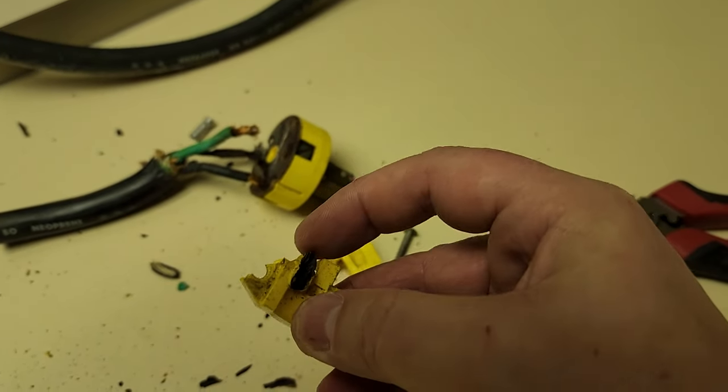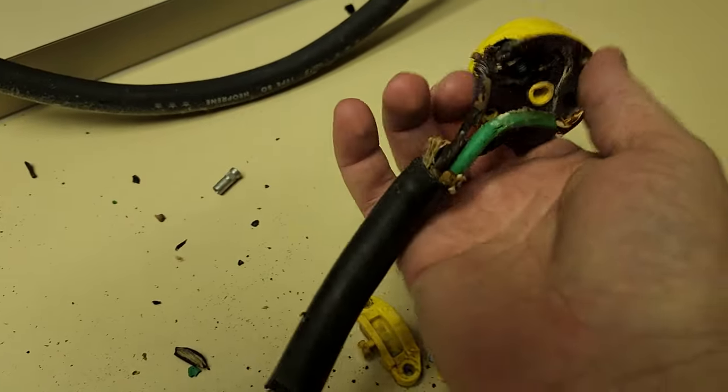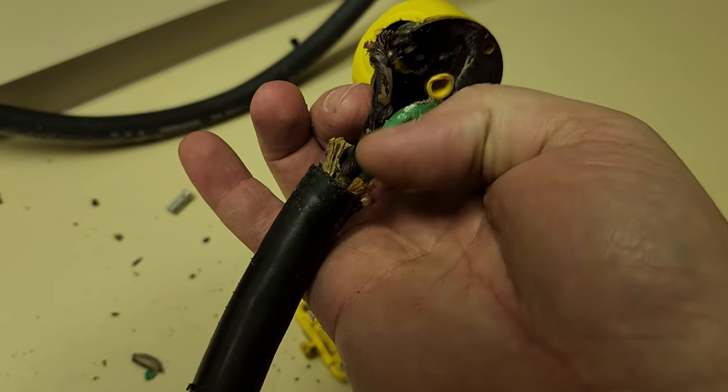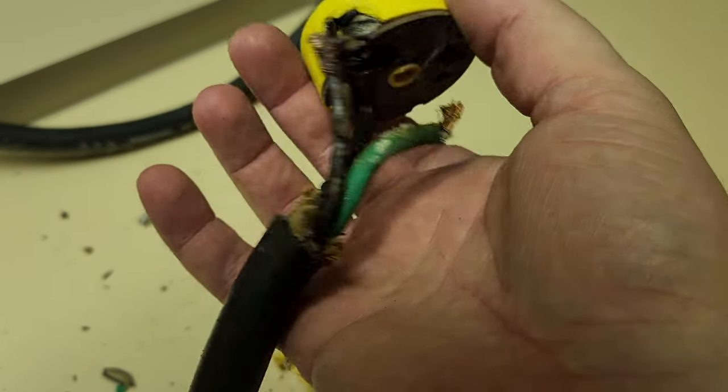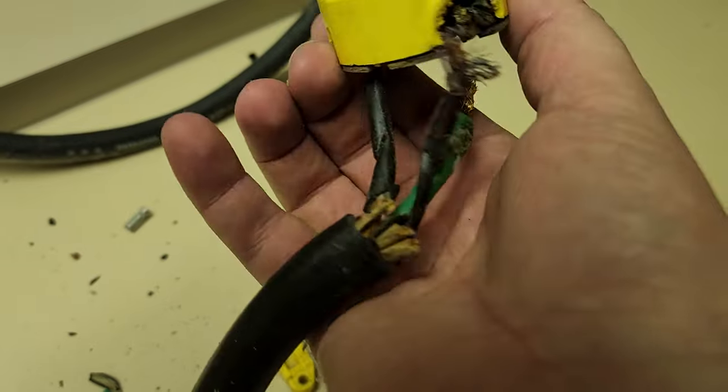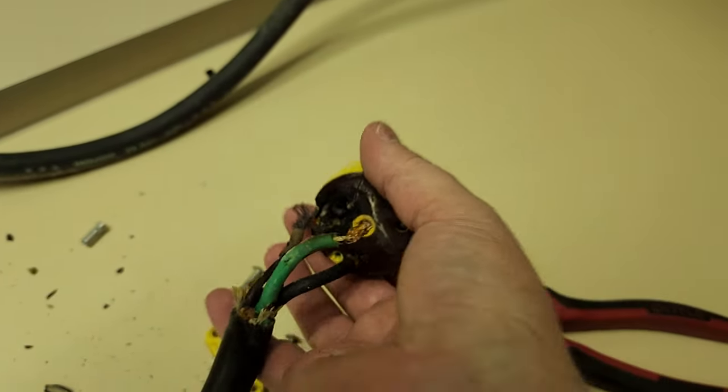This is completely bound up and melted to the plastic. This is all that I could see coming out of the strain relief right here. You can see my L1, L2 and ground. Ground is okay, but L1, L2 those guys got hot hot hot hot.